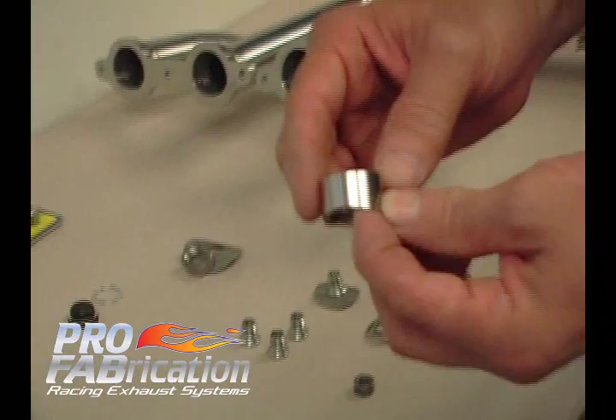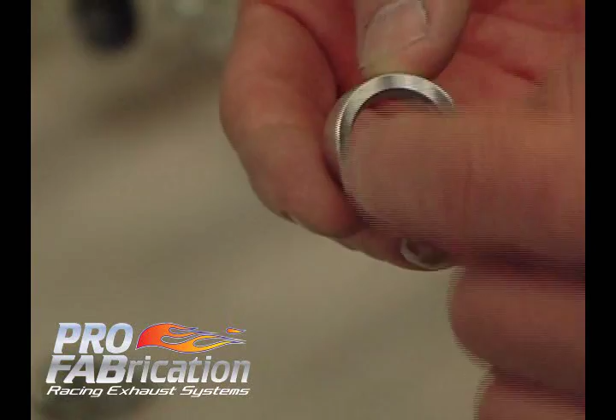We have a fully machined bung right here. We consider this the taller of the two bungs. This will keep the protrusion inside the pipe to a minimum, and it utilizes a counterbore in that bung. So the exhaust gas and the sensor can still work and measure your oxygen inside that tube, but it does not need to protrude deep inside the tube and cause a restriction.